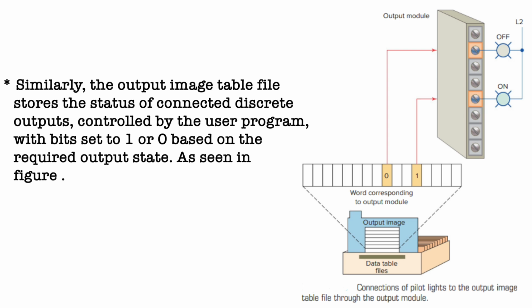Next is the slot number in which it is connected. Here in the input the 1, or in the output the 2, is the slot number. Next is the bit designator. The slash is used to designate the bit number. Here in the input you can see I:1/2, so the 2 is the bit number, and here in the output format O:2/11, 11 is the bit number.